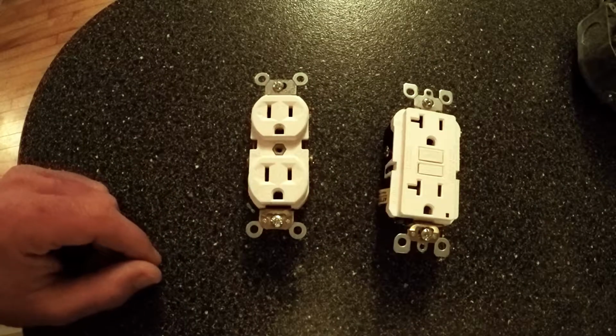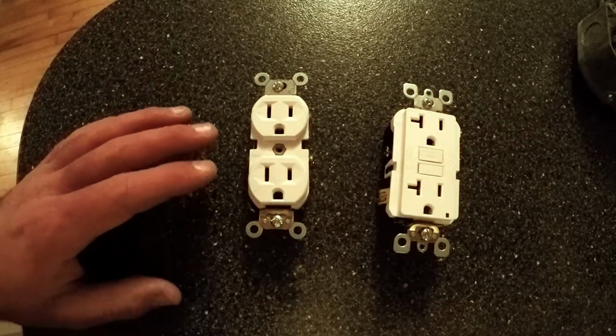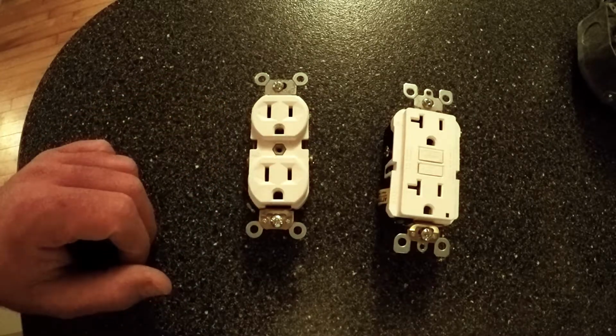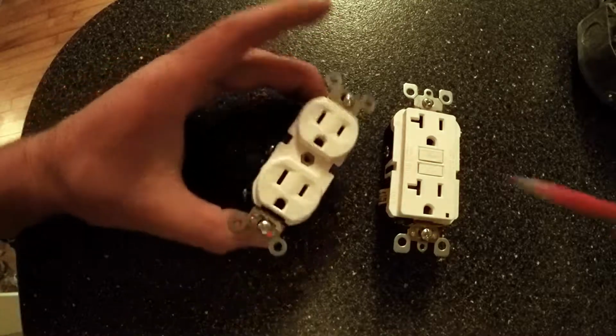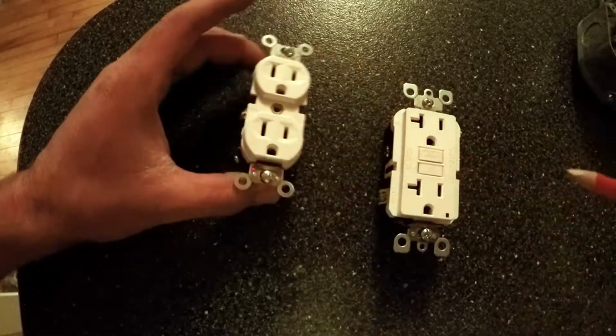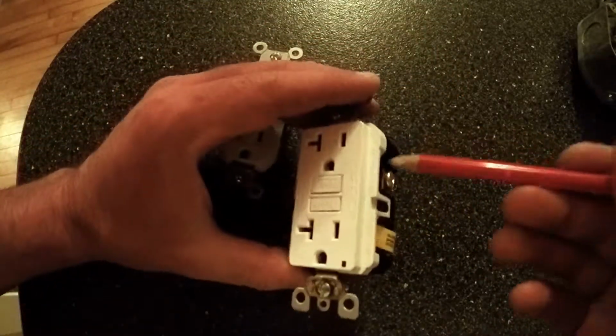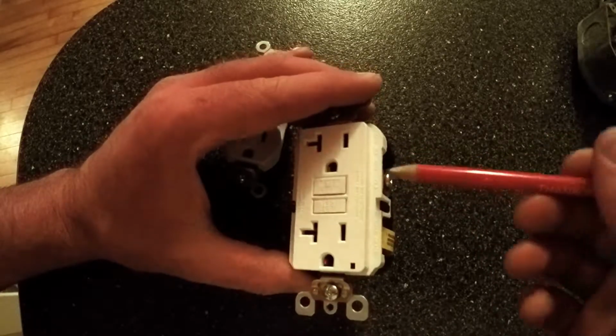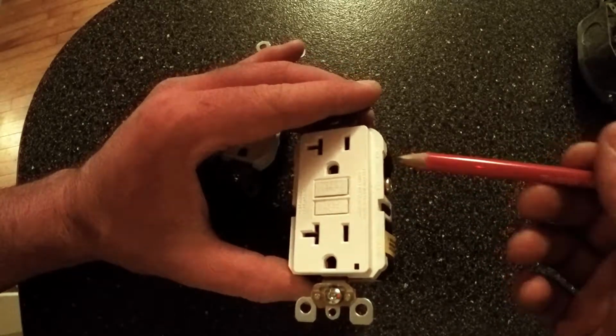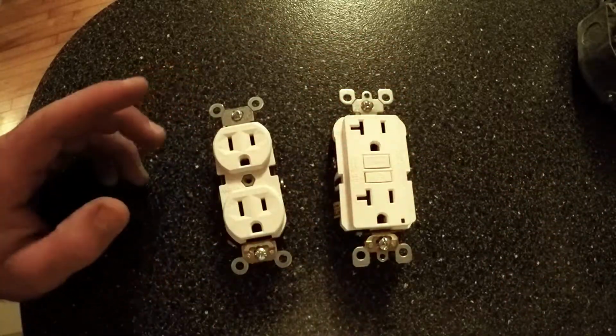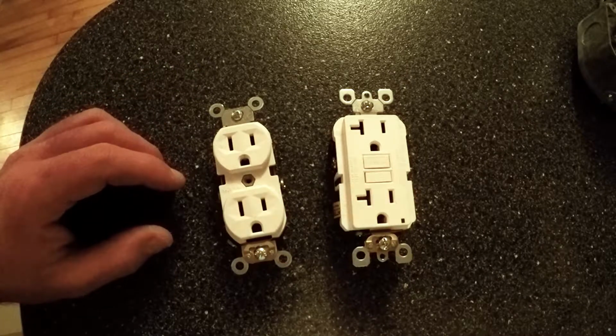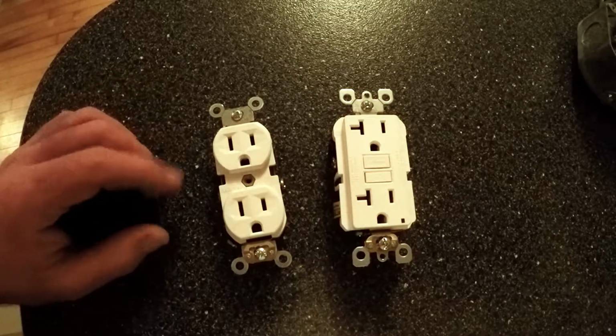Now that you know the rating, you have to get an outlet rated for at least as much as your circuit. In this case, this one here is a 15 amp, 125 volt rating, and this is a GFI outlet - it's printed on the side instead of on the face. This one is a 20 amp, 125 volt rated outlet. The outlet rating has to exceed the circuit rating, otherwise there's a chance you'll run too much power through the outlet and it will heat up and potentially cause a fire.